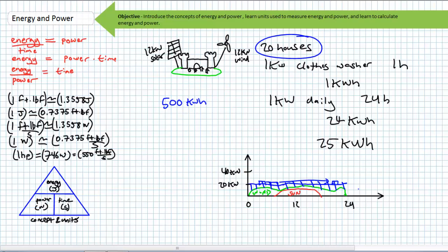Consider a sunny, windy day when both the array and wind turbine operate at full capacity, basically 24 kilowatts, in excess of our normal 20 kilowatt base draw plus 1 kilowatt addition. In this case there's excess renewable energy, and you should spend it all when you've got it—meaning if both are at full capacity, you've got the power to run a couple additional washing machines simultaneously, saving even more fuel when the wind and sun aren't there.